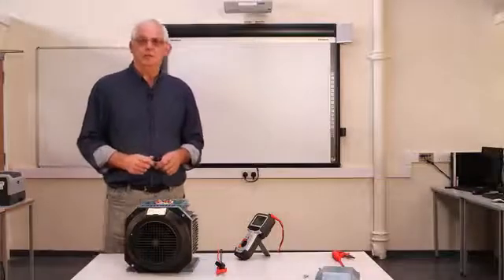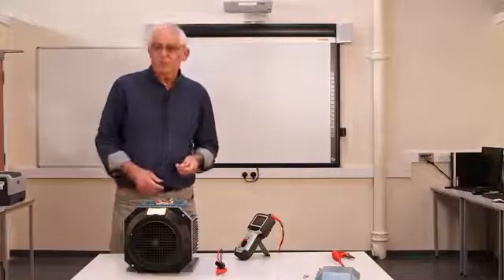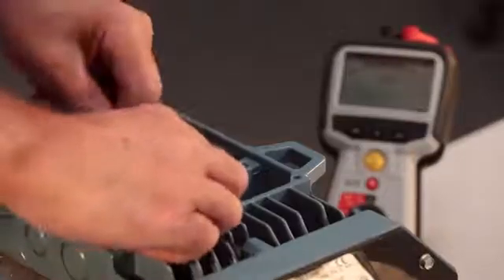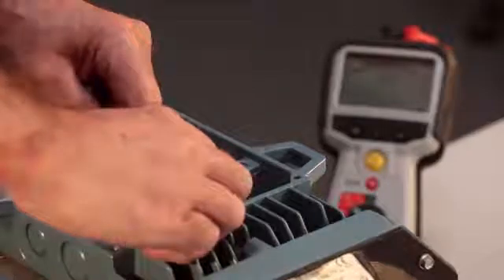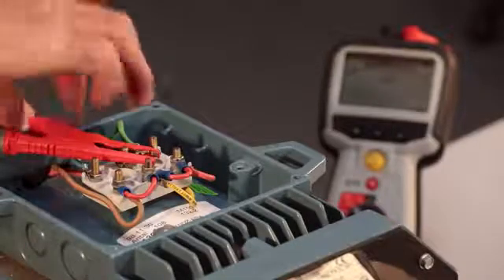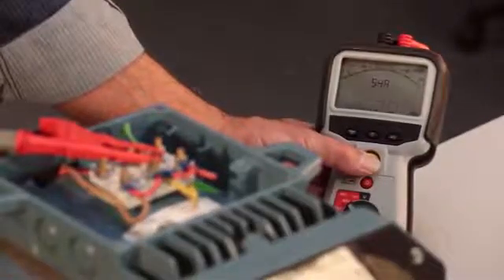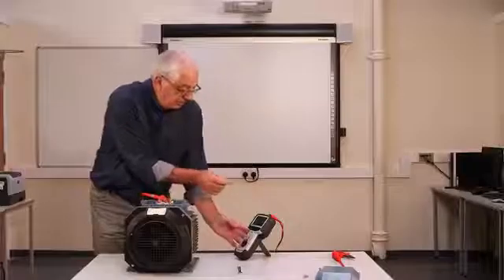So before I start the polarization test, what I really need to do is just earth all of the windings simply to earth just to make sure they're completely discharged. That's very, very important. Once I've done that, I connect the tester like so, connect it to a good earth, push the button, lock it so that it tests for one minute.